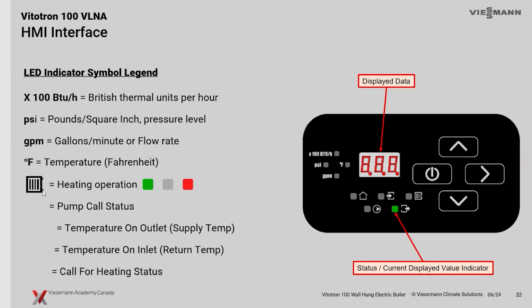So if I've got heating operation, of course, the little radiator here, if it's green, we've got a call for heat. If it's grayed out, then we don't have a call for heat at all. If it's red, we have a call for heat, but the boiler isn't at the set point yet, so it's heating up. The elements are on whenever you see that in red. If the green LED here is on, that means the pump is on. So we see the status of our pump, on or off, here as well.